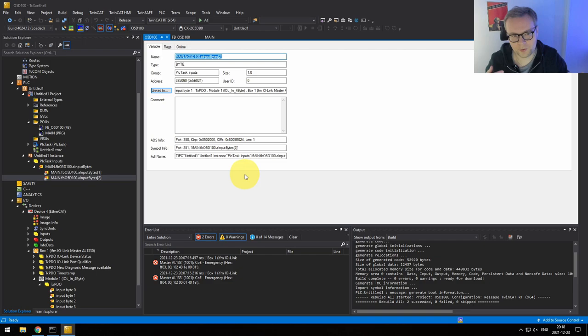This is where the magic happens: we just linked our variables in our code to the fieldbus without writing any software to get EtherCAT up and running. Getting an EtherCAT master to work in TwinCAT is really very easy. Now we have these guys linked — you can see the two arrows indicating that these 2 bytes are actually linked to something in the PLC code. The next step is to convert those bytes into the values we want.